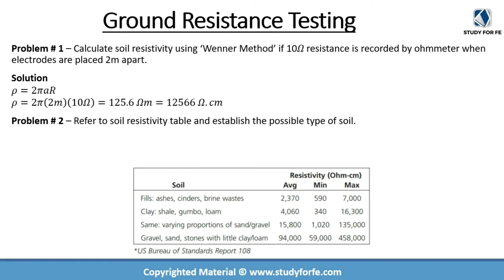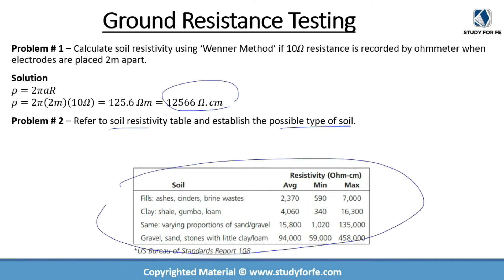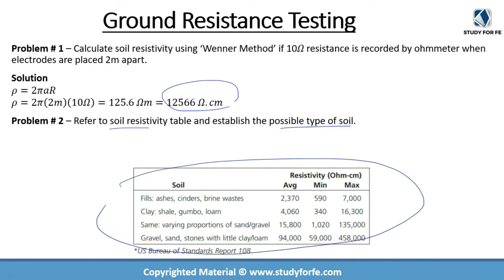Problem two asks us to refer to the soil resistivity table and establish the possible type of soil. The calculated resistivity of 12,566 ohm-centimeter falls under the category of sand and gravel mixture, which has a resistivity range of 1,020 ohm-centimeter up to 135,000 ohm-centimeter. It's not completely clear-cut as it could also fall under varying proportions of sand and gravel, but it is not a swampy area and has relatively higher soil resistivity.